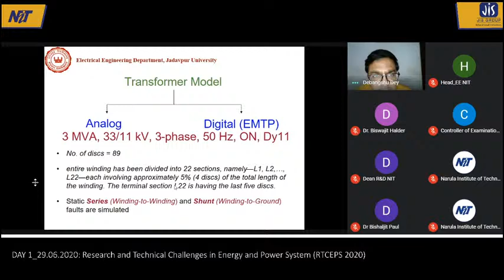And as it is a model, we can create the fault at different places. That means, in a real life transformer, what is the problem? In a real life transformer, the manufacturer will not disclose the design specifications and other details of the transformer. So when you are going to design a system that will predict the condition of the insulation, we have to test the system on some transformer model. And this one is the transformer model, where we can create deliberate faults in certain windings. Deliberate fault means we can short circuit two windings. If insulation failure occurs, what will happen? Then the different turns of the coil will be short circuited.